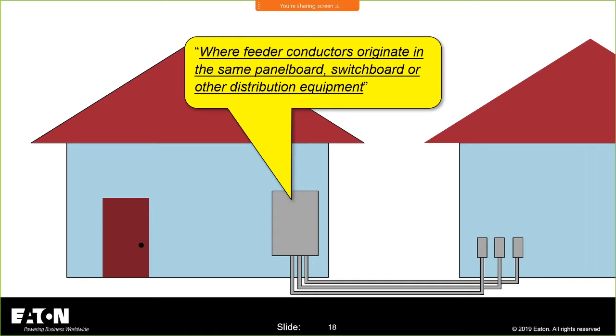But the key here is to note that all of those feeders that go out to that separate structure have to originate in the same panel board, switchboard, or other distribution equipment. And when they terminate, they have to terminate in a single disconnecting means. Not more than 6 feeders are permitted. And then you have to label that disconnecting means with what it supplies. So where you're doing that, it has to be marked to indicate the load that is served.